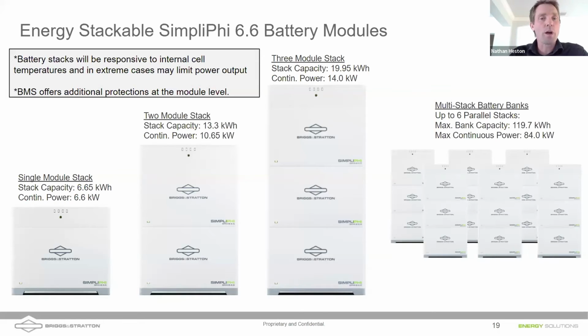a 13.3 kilowatt hour stack can output over 10.5 kilowatts of power. And then a 3 stack of these batteries, a triple stack like this, can output 14 continuous kilowatts of power. And as John mentioned earlier, the Sol-Ark 15k from battery alone is capable of 12 kilowatts of continuous power. So a single stack of 3 of these batteries can offer you the full capabilities of Sol-Ark 15k in terms of power output.